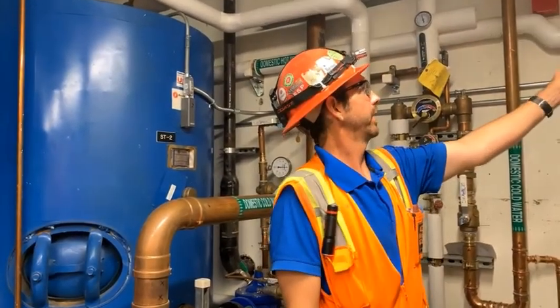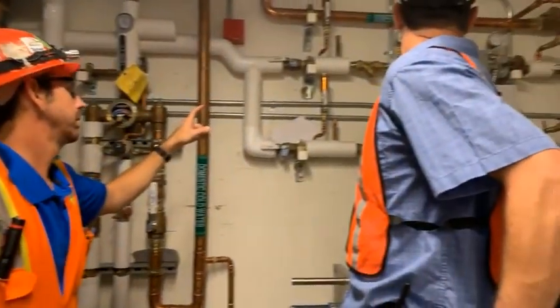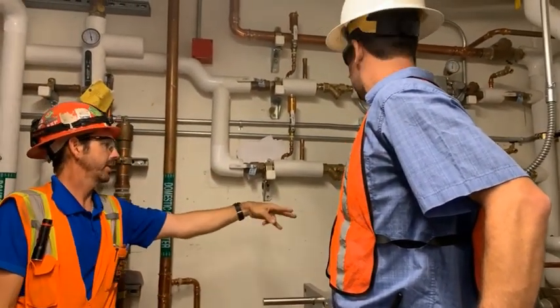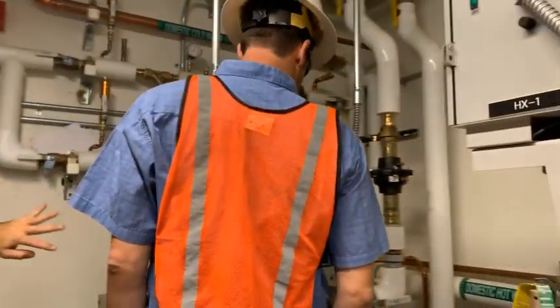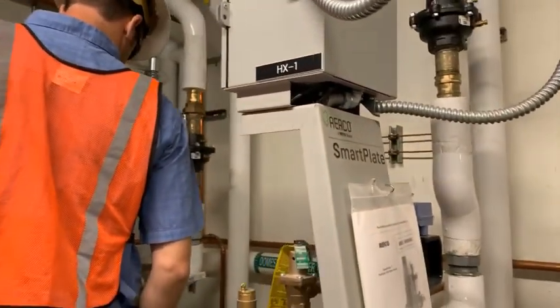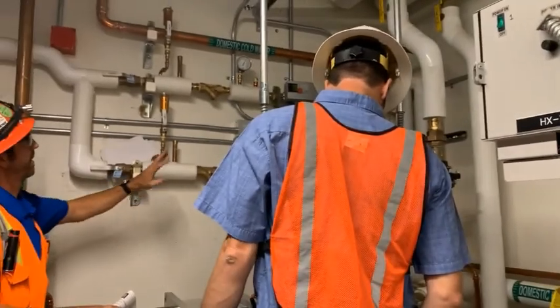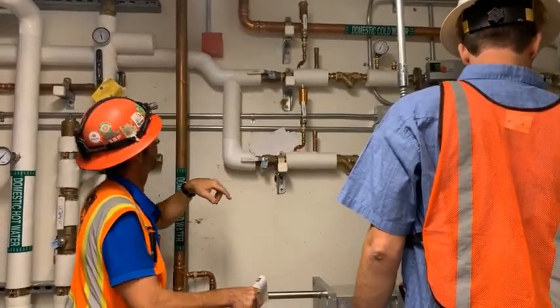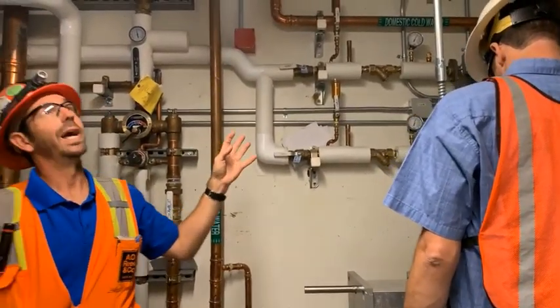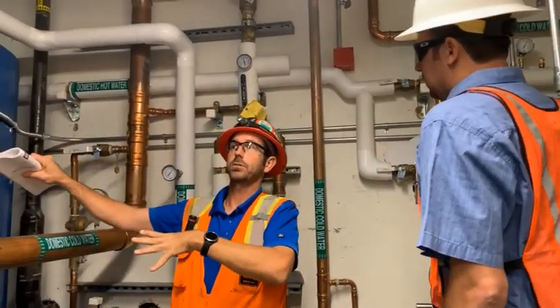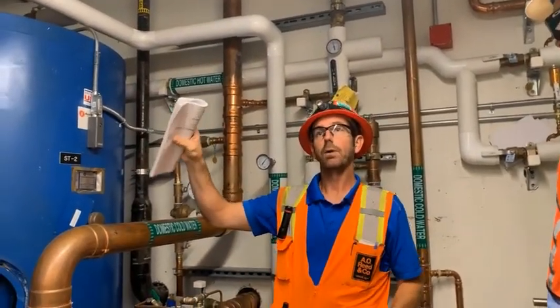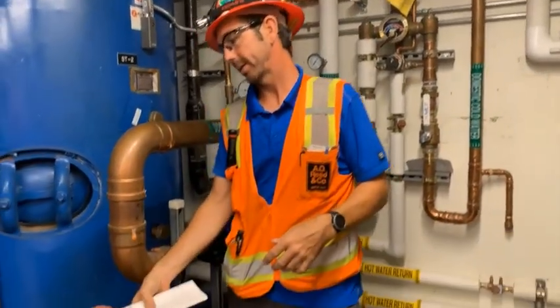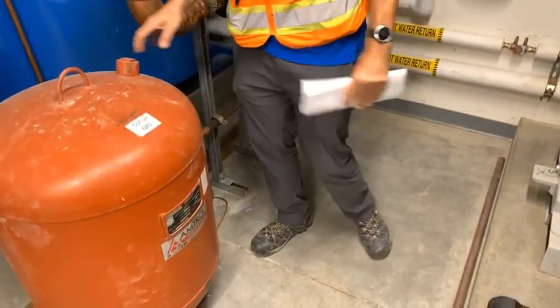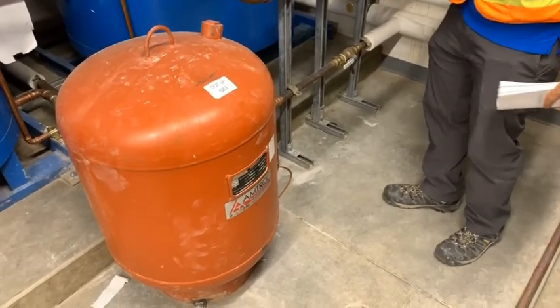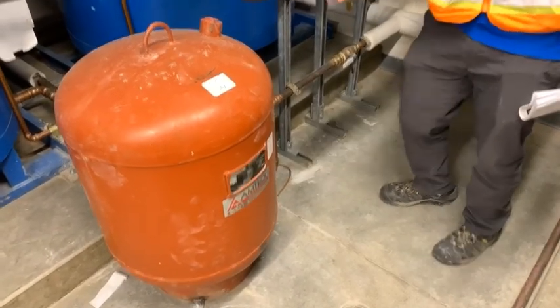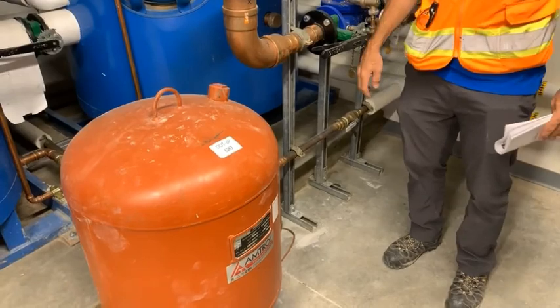Then we have hose bibs over here on the outlet of the pumps. Shut-off valves at the heat exchanger on both the domestic and the heating hot water side. Again, we'll talk about the switches and the pumps tomorrow. Any questions on the stuff that's behind me, the storage tanks? Real quick too, this expansion tank is for the domestic system, the domestic hot water system. Okay, do you guys all know how the expansion tank works and how to check the charge on it?